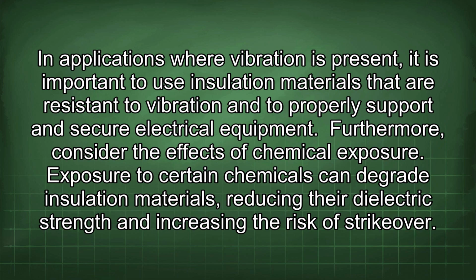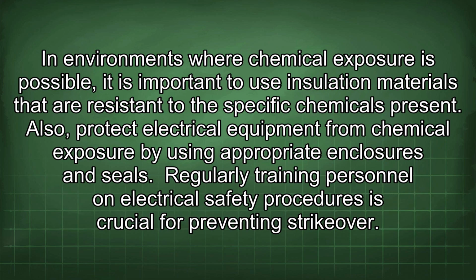Furthermore, consider the effects of chemical exposure. Exposure to certain chemicals can degrade insulation materials, reducing the dielectric strength and increasing the risk of strikeover. In environments where chemical exposure is possible, it is important to use insulation materials that are resistant to the specific chemicals present. Also, protect electrical equipment from chemical exposure by using appropriate enclosures and seals.